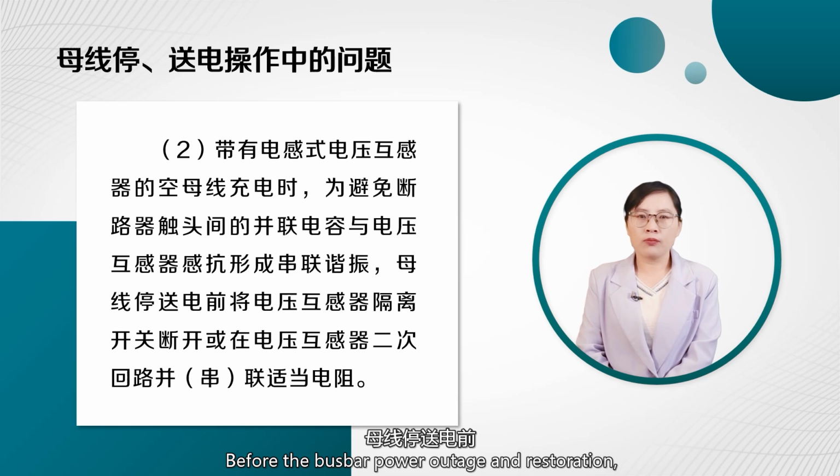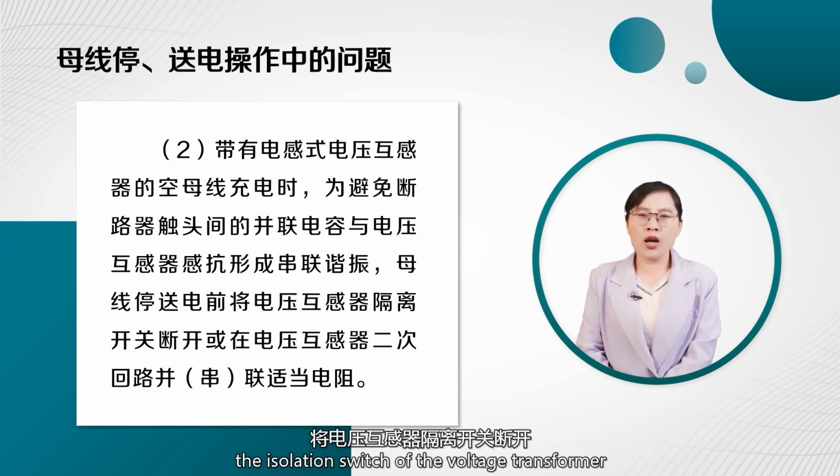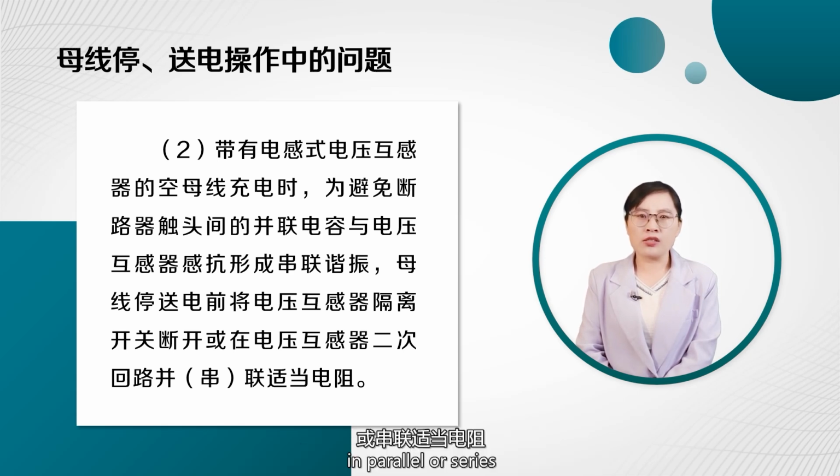Before the busbar power outage and restoration, the isolation switch of the voltage transformer should be disconnected, or an appropriate resistor should be connected in parallel or series in the secondary circuit of the voltage transformer.